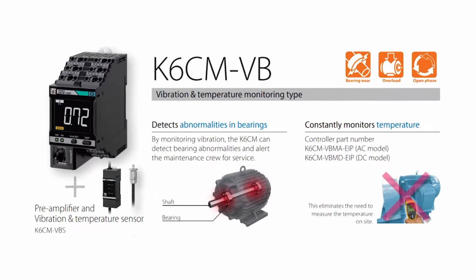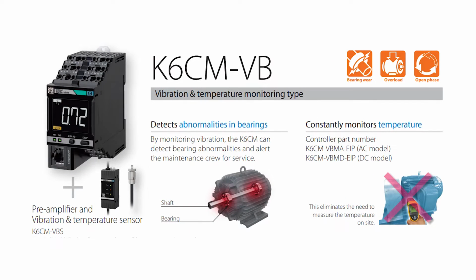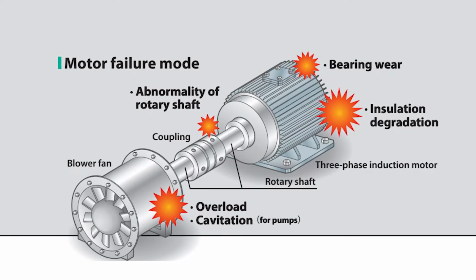Moving on in today's showcase, we have the K6CM series 3-phase induction motor condition monitors. So traditional 3-phase motors are complicated, costly, and time-consuming to maintain. Normally an engineer has to use lived experience to catch issues like bearing wear, insulation degradation, rotary shaft abnormalities, overload, and/or pump cavitation.